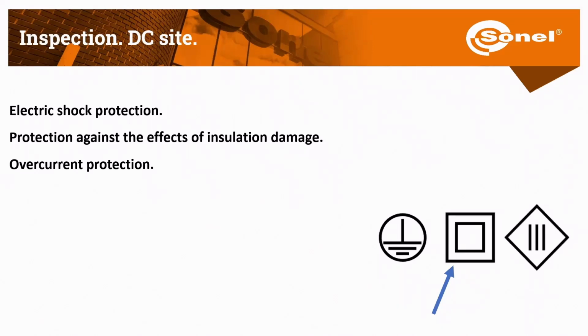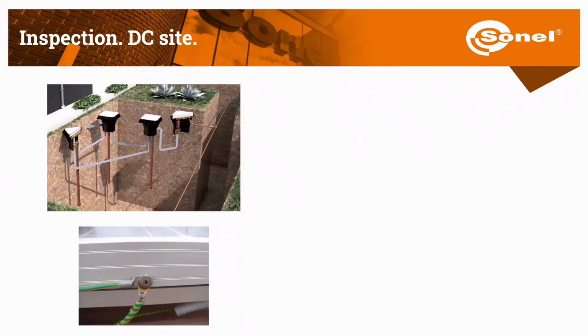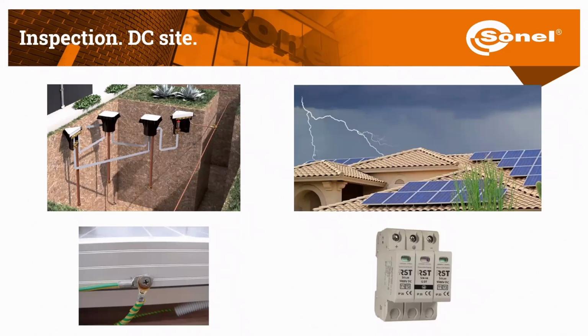We have to follow some regulations according to the standard 62446 to make sure that the whole equipment is doubly insulated and has overcurrent protection. For example, the DC side has a varistor and LPS, lightning protection systems. We have the bonding. We have the connector. Each panel is connected together with continuity cables. Everything should be grounded, and in the case of special premises, it should also be protected by the lightning protection system.